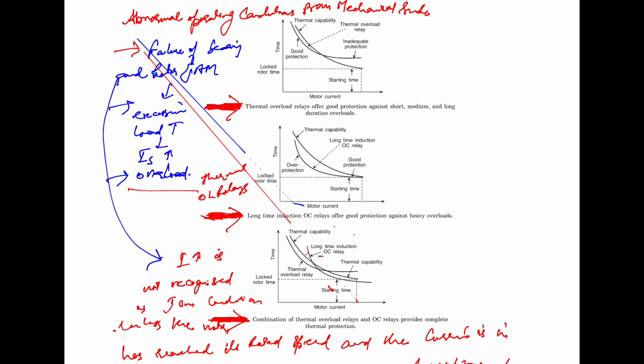Now from this figure you will observe that the thermal overload relay provides good protection against the short, medium and long duration overloads. However, it will provide inadequate protection, as you have seen, when the load is very large. So this is the thermal capability curve, and this is the thermal overload relay. However, from this graph you will see that the long time overcurrent relay offers good protection against the heavy overload. It provides good protection against the heavy overloads, as you have seen from this time current, motor current characteristics.